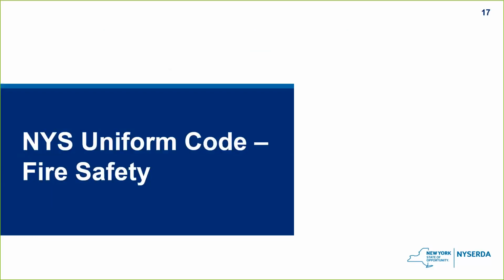So, of course, any technology is going to come with its own risks. The biggest concern you've probably heard with energy storage and lithium-ion systems in particular is fire. Lithium-ion batteries, after experiencing abuse of some sort, be it overcharging, physical damage like puncture or crushing, or exposure to extreme heat, can experience a process referred to as thermal runaway. Essentially, once one of these batteries is compromised, it can begin to overheat, changing the dynamics inside the battery, causing further heating. It's like a positively reinforcing process, and we refer to this as thermal runaway. And once it's happening, it's really difficult to stop it.